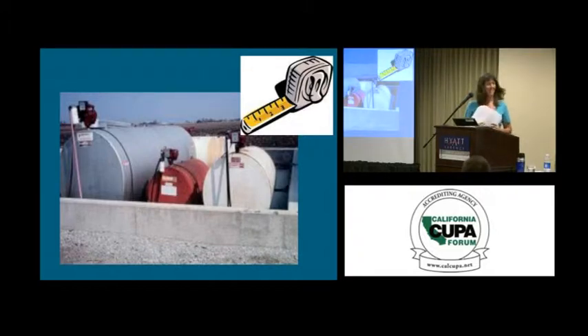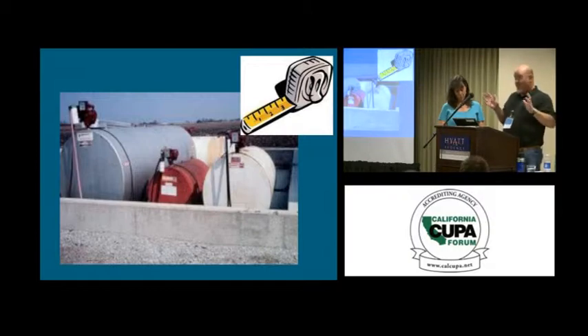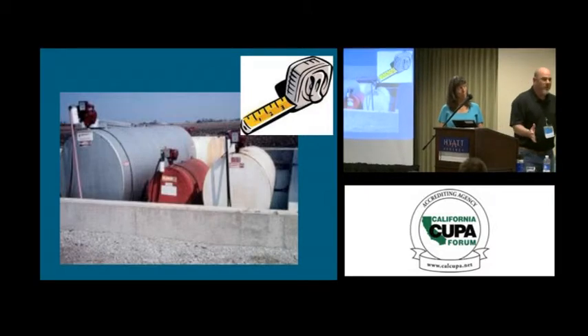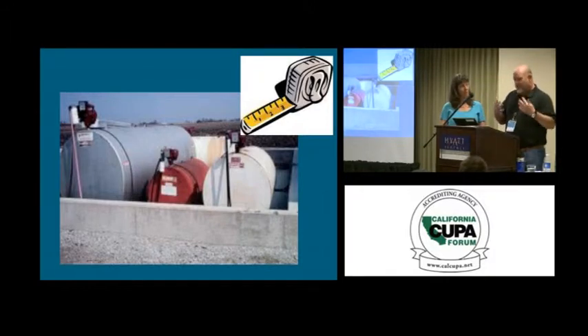Yes, please. It's okay. So I think a couple of points need to be clarified on the general containment requirements. If a facility operator is manipulating, moving, or otherwise using a drum, and it's within their vision and control, would they need to have a general containment, somebody with a sorbent or a dike or a berm of sorts to follow them around? No, there's not a containment requirement while it's under operational control.